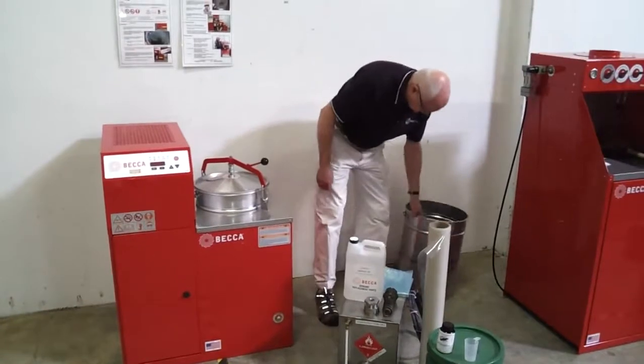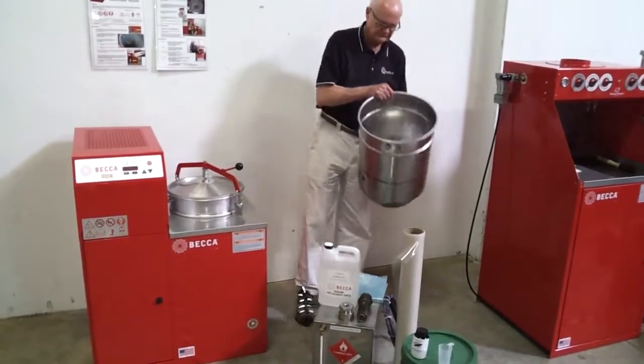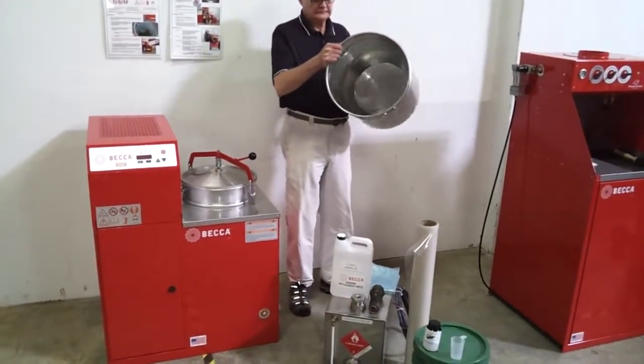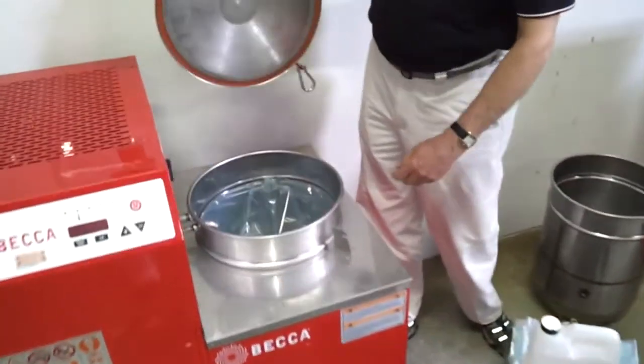The features include a wide mouth stainless steel boiler tank with a capacity of 6 gallons on the HC high capacity model and 3 gallons on the SC standard capacity model. The insulated tank has a double wall design with a wide mouth and chamfered bottom for ease in removing the nylon liner bag with the still bottom and installing a new liner.